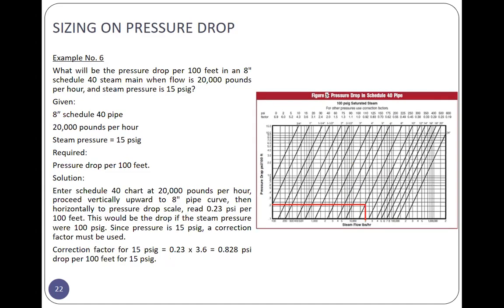Example number 6. What will be the pressure drop per 100 feet in an 8 inches schedule 40 steam main when flow is 20,000 pounds per hour and steam pressure is 15 psi gauge? So given is the pipe size, schedule 40, 20,000 pounds per hour, steam pressure is 15 psi gauge. The required is the pressure drop per 100 feet.